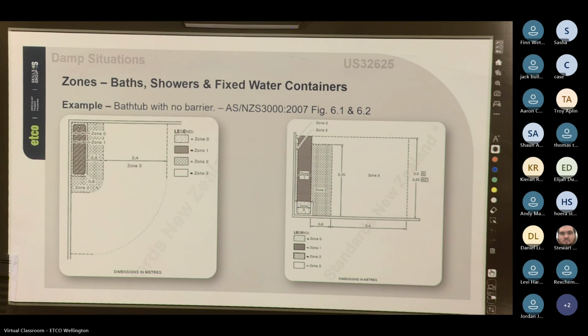Cool. So these are the actual pictures that you have in 3000. So if you look at them, this is figures 6.1 and 6.2. So 6.1 is a top-down view of a bathtub inside of a bathroom. Now, this is a pretty big bathroom, but it's obviously there to give us a good reference picture. And then 6.2 is the same, except a vertical. Now, if you notice here on 6.2, you have an A and an NZ next to two different numbers. So in Australia, they go 2.4 for zone 1. And in New Zealand, for zone 1, we go to 2.25. So in New Zealand, it's from the floor.